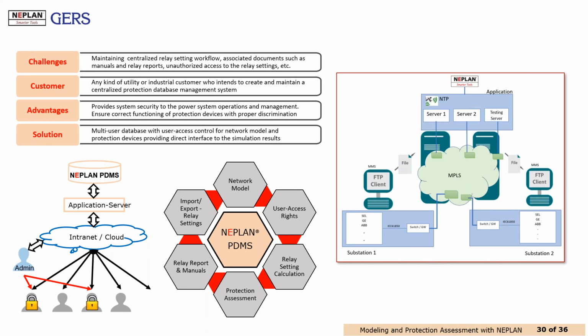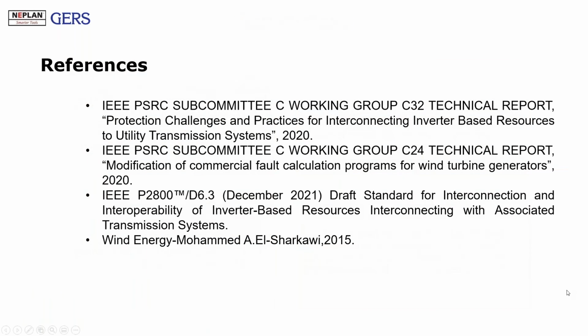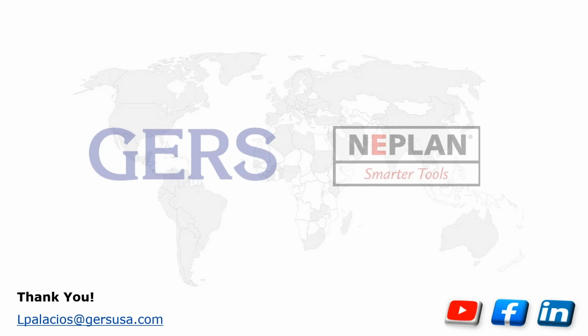Okay, great. We have one other question here. Can the NEPLAN protection assessment also be used in distance protection coordination? Absolutely. In this webinar, I presented the example of the overcurrent protection, since that is one of the selective protections, but also the protection assessment works very, very good for distance protection. In that case, the coordination is done using the different zones, zone 1, 2, and 3, and the protection assessment will check if the tripping times, depending on the fault location, are according to the topology or not. But yeah, the protection assessment works very good also with the distance protections.